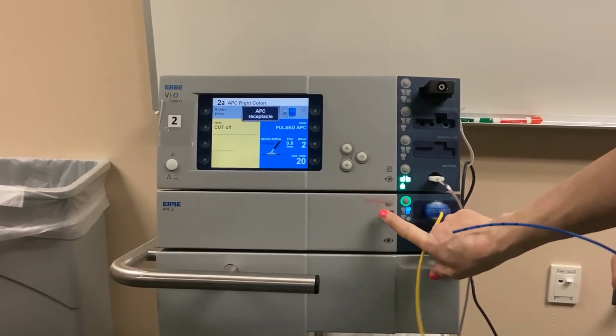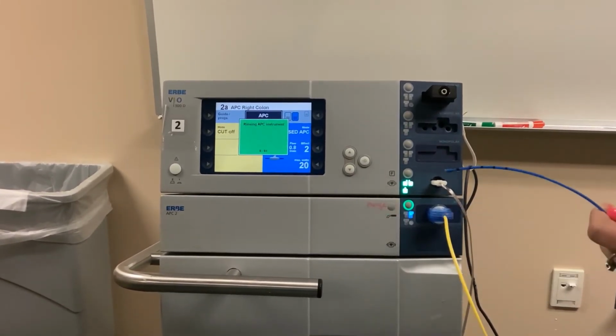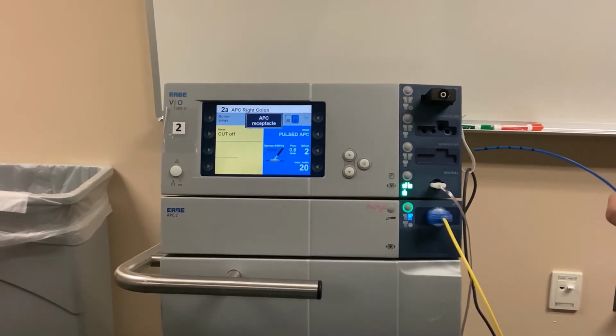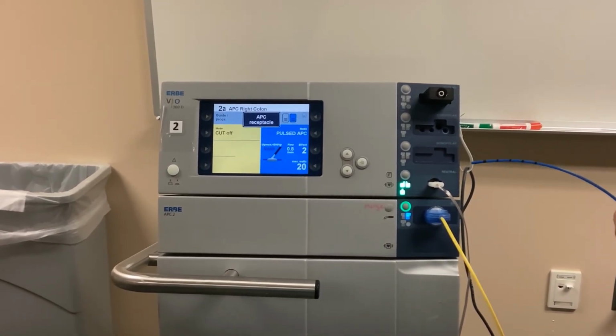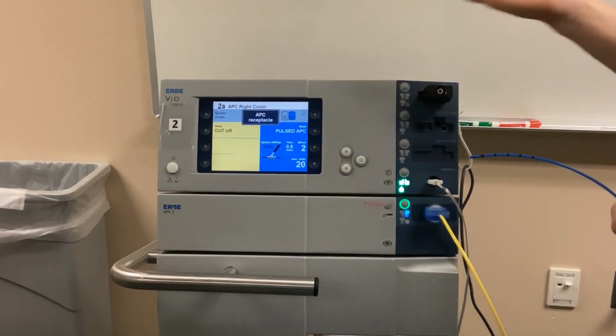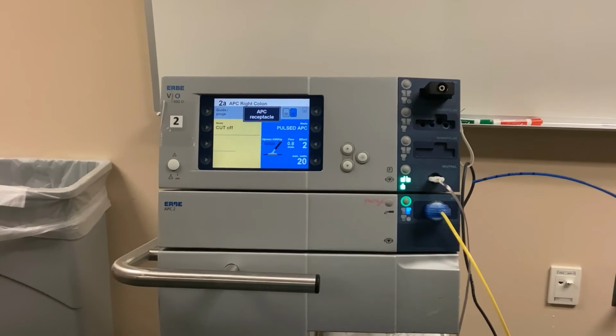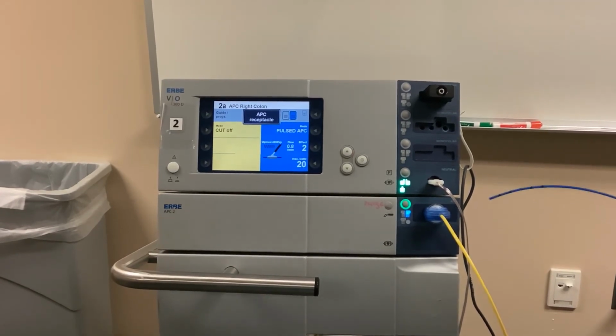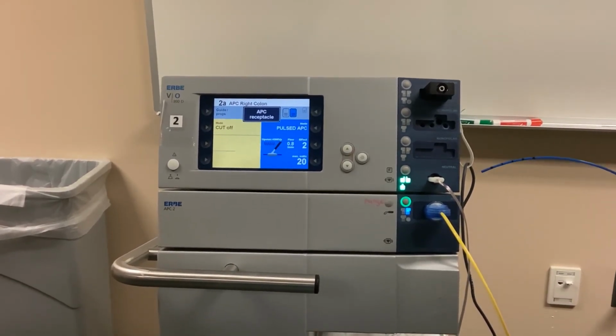After the probe is visible inside the patient, the doctor will want you to purge the device. This ensures the device is filled with argon gas. Passing the device down the scope displaces some of that gas. Again, verbally confirm your settings are correct, and then the doctor will administer the APC using the foot pedal and complete the procedure.